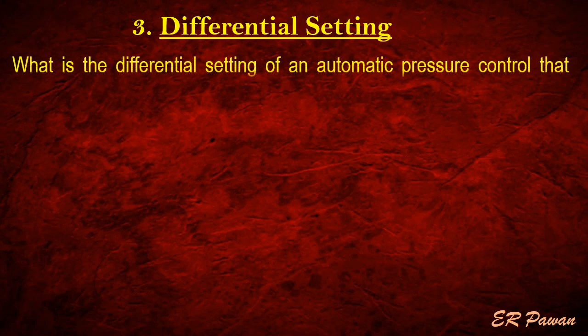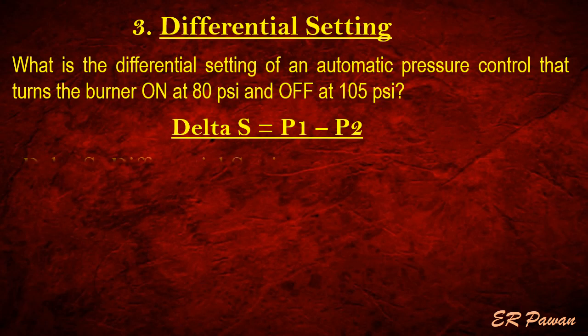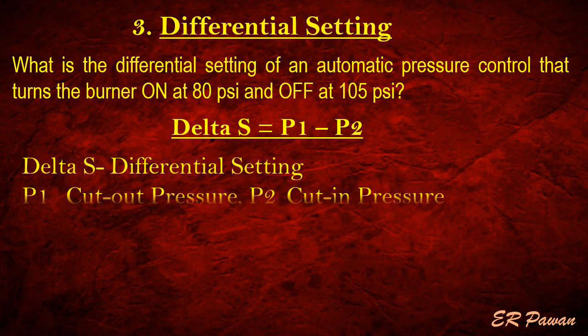Formula 3 — Differential Setting. What is the differential setting of an automatic pressure control that turns the burner on at 80 pounds per square inch and off at 105 pounds per square inch? Delta S equals P1 minus P2. Where Delta S = differential setting, P1 = cut-out pressure, P2 = cut-in pressure. Let's put the value in the formula.